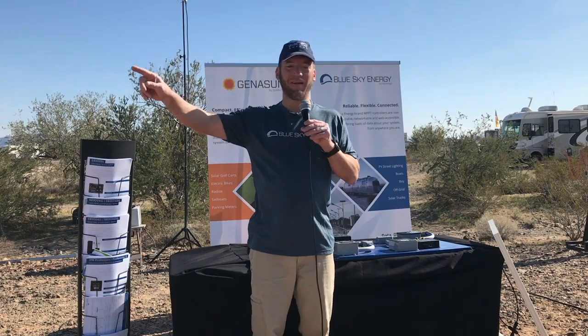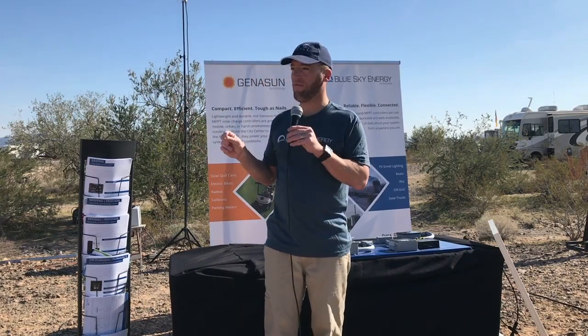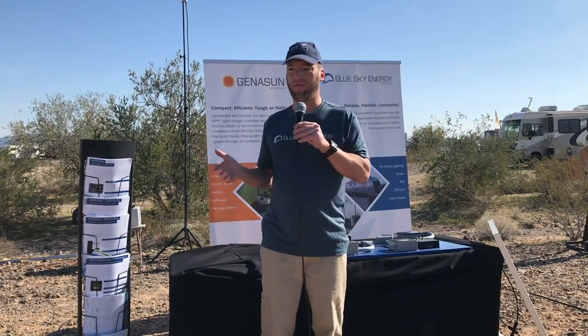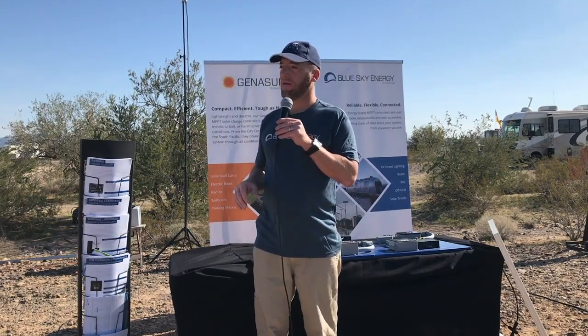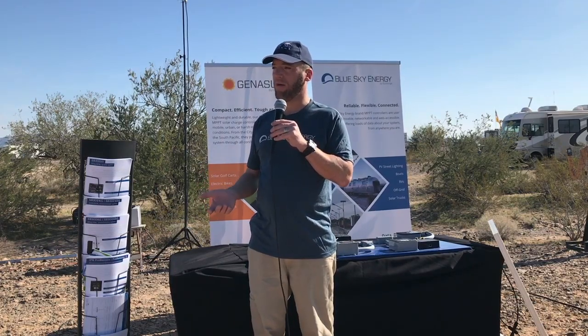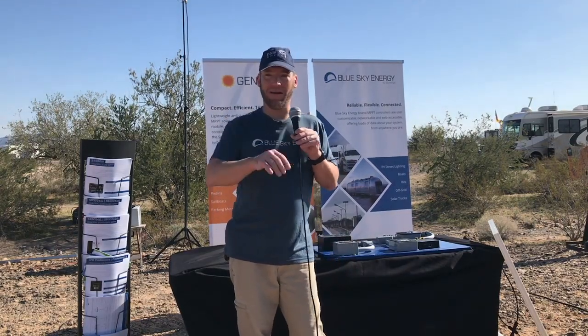On his question about fusing, what kind of fuse and how many amps? You want to rate your fuse about 10 amps over your controller's max output. So if I have a 30 amp controller, I'll put in a 40 amp fuse. This matters especially if you're using a DC breaker like a Blue Sea breaker, since you don't want to run those at their max. If something tragic happens, like water getting on your controller or a wire shorting, your battery has hundreds of amps available, so the fuse is really there for short circuit protection. I'd rather go a little over on fuse size to avoid issues. Speaking about fuses, not all fuses are created equally.